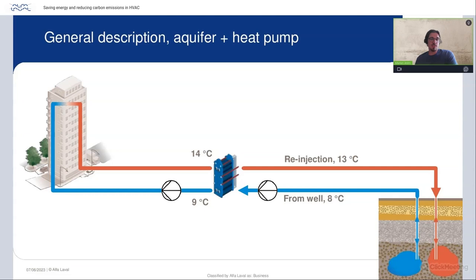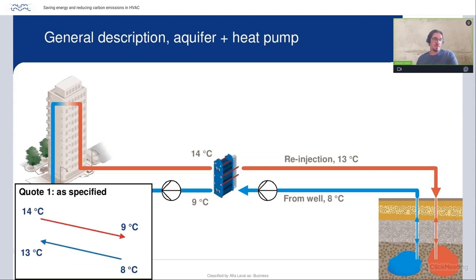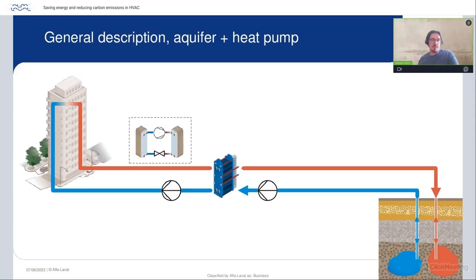So this is the duty that the unit has been specified to do, which we describe like this: 14 to 9 on the hot side, 8 to 13 on the cold side. This is what was specified in a project, a quite common setup in, for instance, the Nordics, where I live myself. And this type of installation would typically have a heat pump or a chiller as well to support the free cooling, and in the winter time to use it as an energy source.